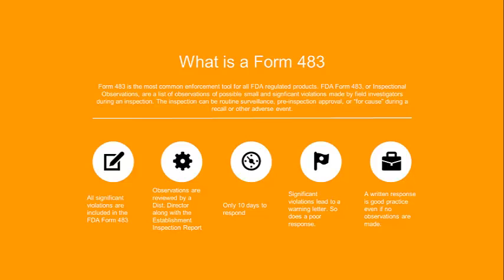Remember, the FDA's mantra, what it operates under, is if it's not recorded, it doesn't happen. And that's what the field investigators will tell you when they come into a facility asking for records. So it's important to apply that mantra to the agency that's giving it to you. So always provide a written bookend, recapping that experience and recapping the observations and the conversations you had with the investigators. It's very important, even if there isn't a formal FDA Form 483 issued.